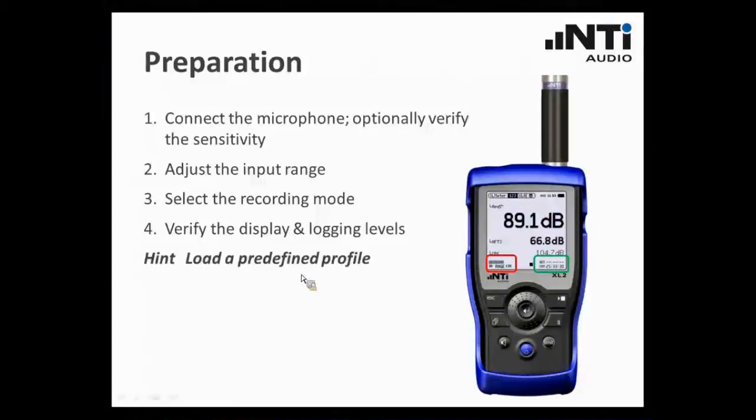We strongly recommend to save all these settings in a profile and load it before you start the measurement. The main reason is it takes off the burden of adjusting everything correctly just before the measurement starts, so you can do that quietly in your office the day before, whenever you have time. It's just much less stress. You can even download predefined profiles from our website. We are supplying them for various standards. The details of all these settings, by the way, have been presented in previous webinars, so I don't want to spend much more time on this aspect here.